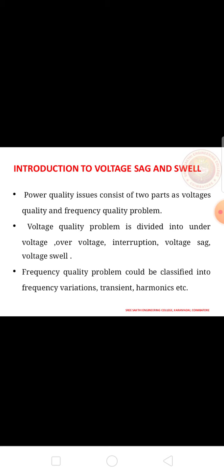The two power quality problems identified to be major concerns to customers are voltage sags and harmonics. But in this unit, the discussion will focus on voltage sag. Voltage variations such as voltage sags and interruptions are the two most important power quality concerns of our customers. Next one, estimating voltage sag performance. It is important to understand the expected voltage sag performance of the supply system, so that facilities can be designed and equipment specifications developed to assure the optimum operation of production facilities.